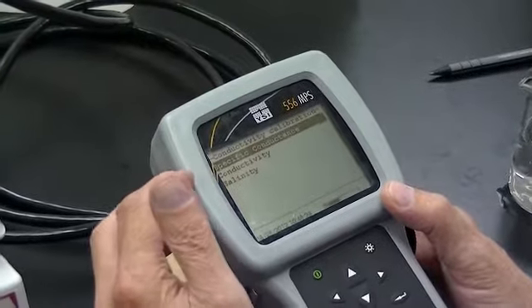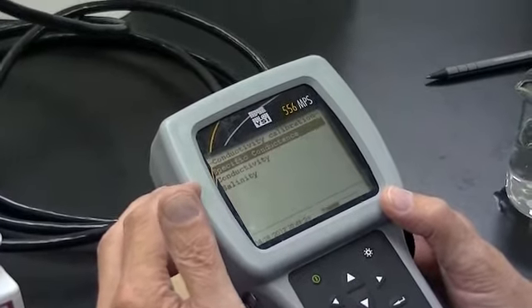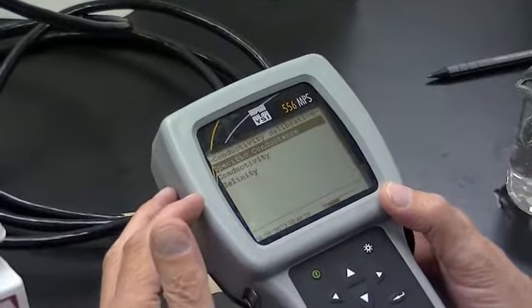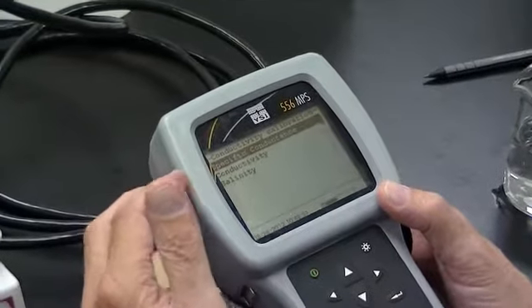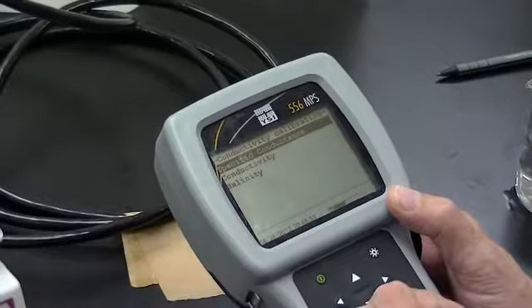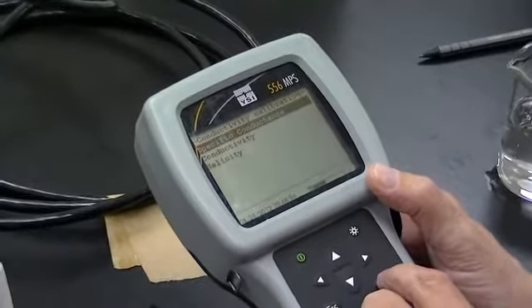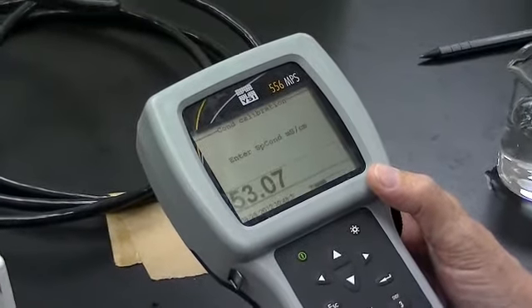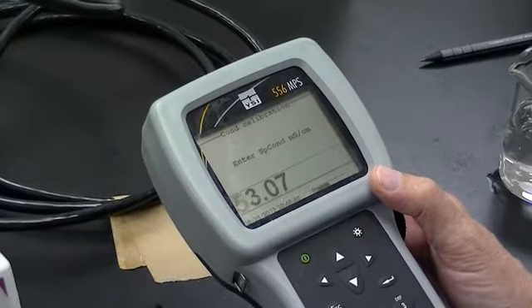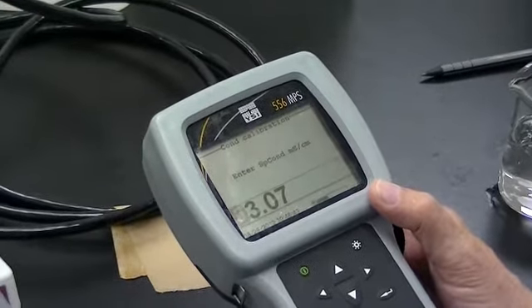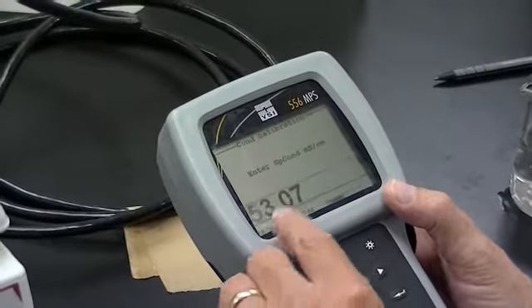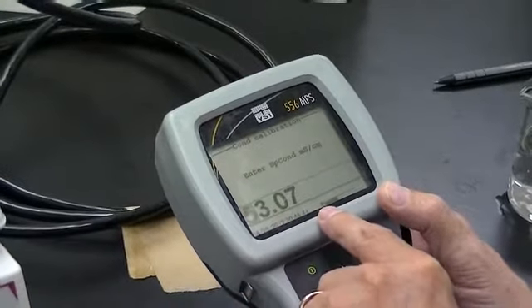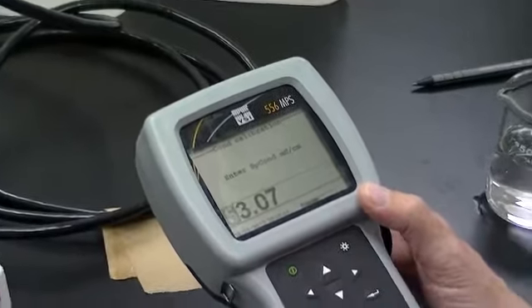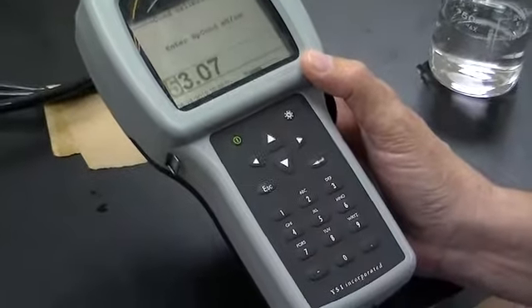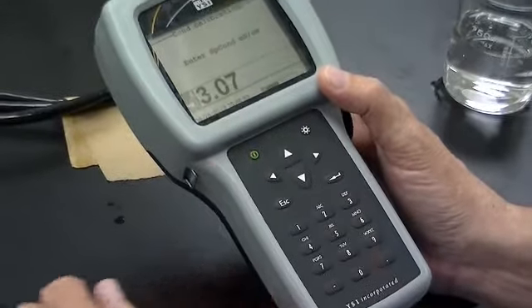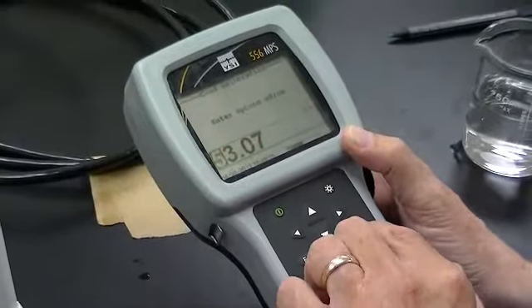We're calibrating it for conductivity, so you just hit return again. Now you have three choices: specific conductance, conductivity, and salinity. Now we're going with specific conductance. So you hit return again, and now you see a number that says 53.07. If the number doesn't say 53.07, then use the keypad to make it say that number. If it does say it, then just go ahead and push return.